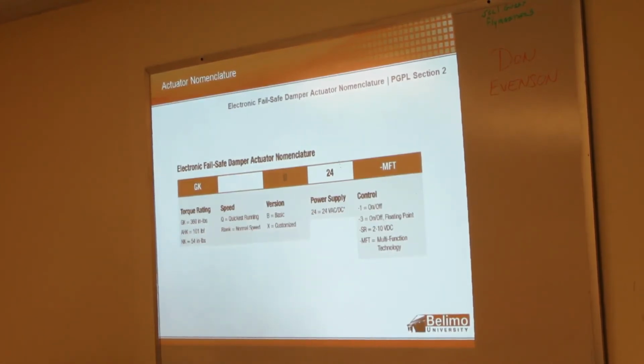Electronic failsafe. I mentioned this earlier. This is where we have a capacitor bank built into the actuator. So rather than a mechanical spring, upon a power failure, the capacitors drive the actuator to its fail-safe position.